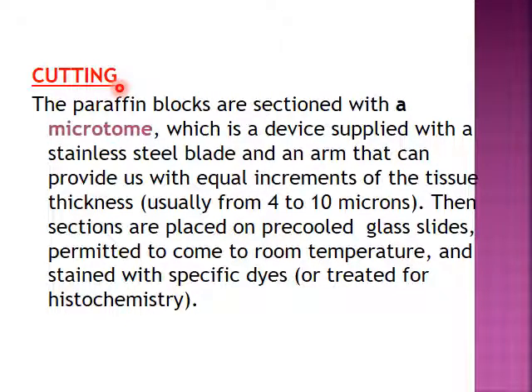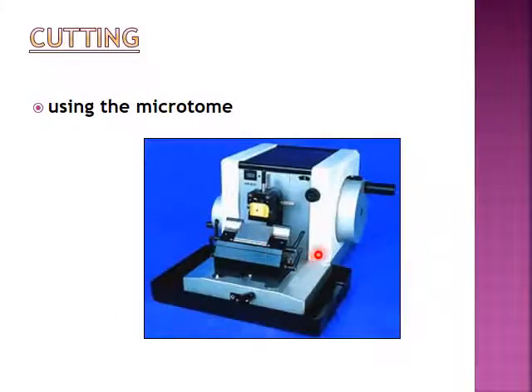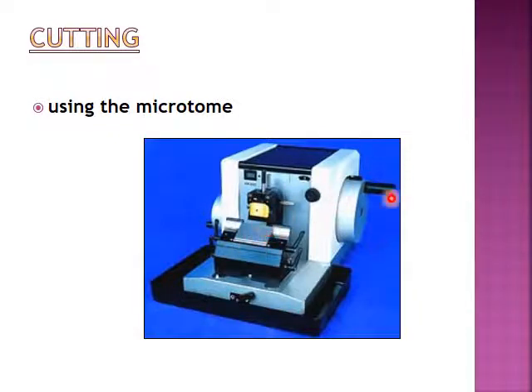Cutting: the paraffin blocks are sectioned with a microtome, which is a device supplied with a stainless steel blade and an arm that provides equal increments of the tissue. The thickness of the sections is usually 4 to 10 microns. The sections are then placed on a pre-cooled glass slide, permitted to come to room temperature, and then stained with a specific dye or treated for histochemistry. The microtome has a tissue block, a blade, and an arm used for cutting.